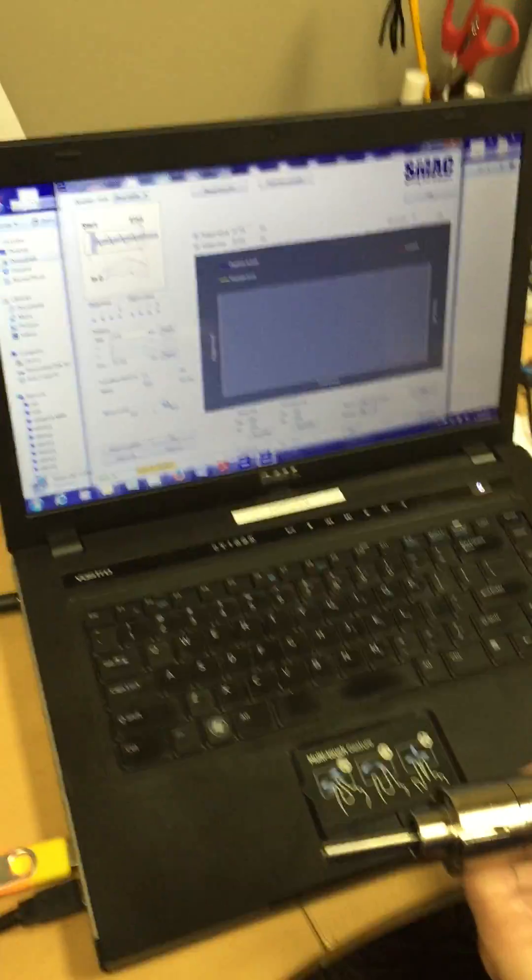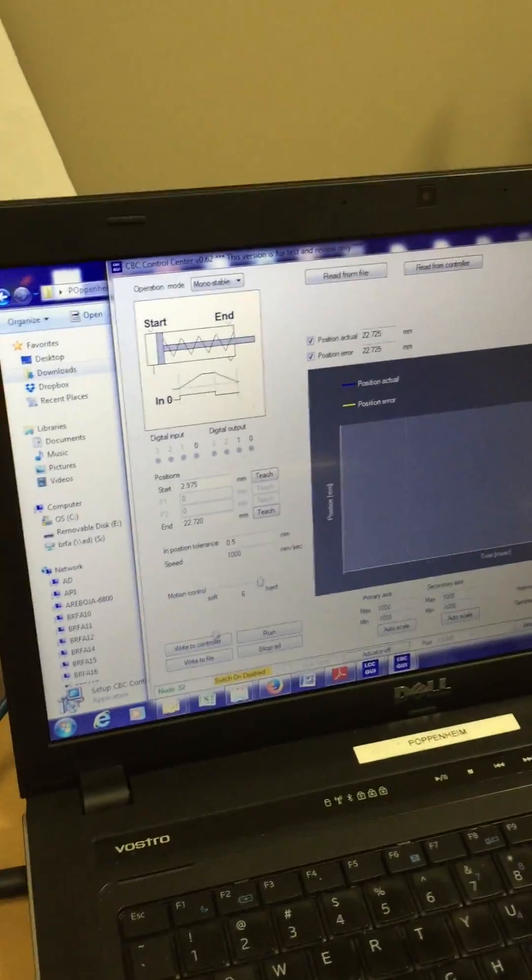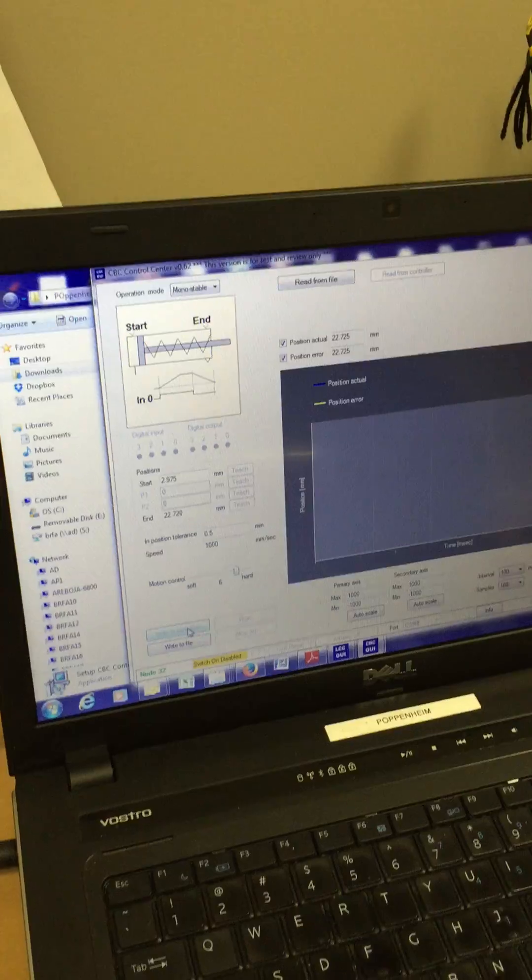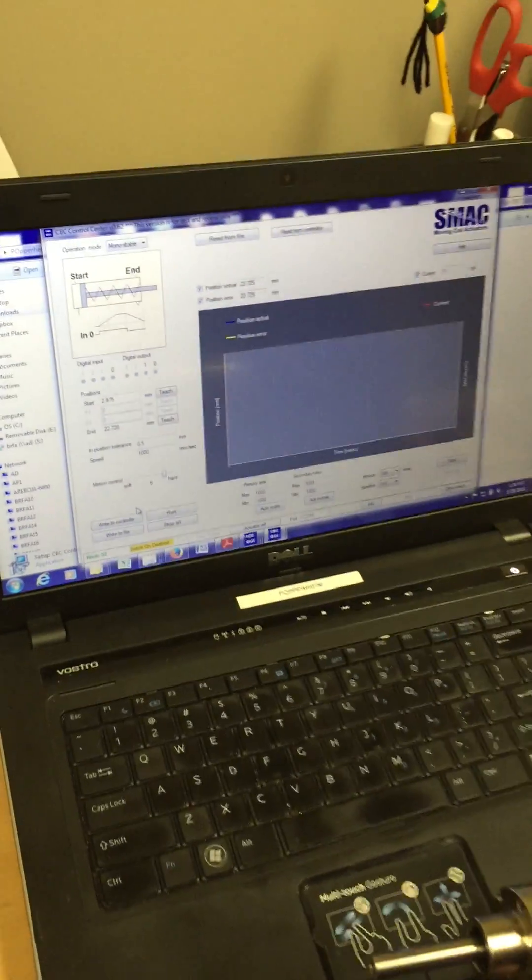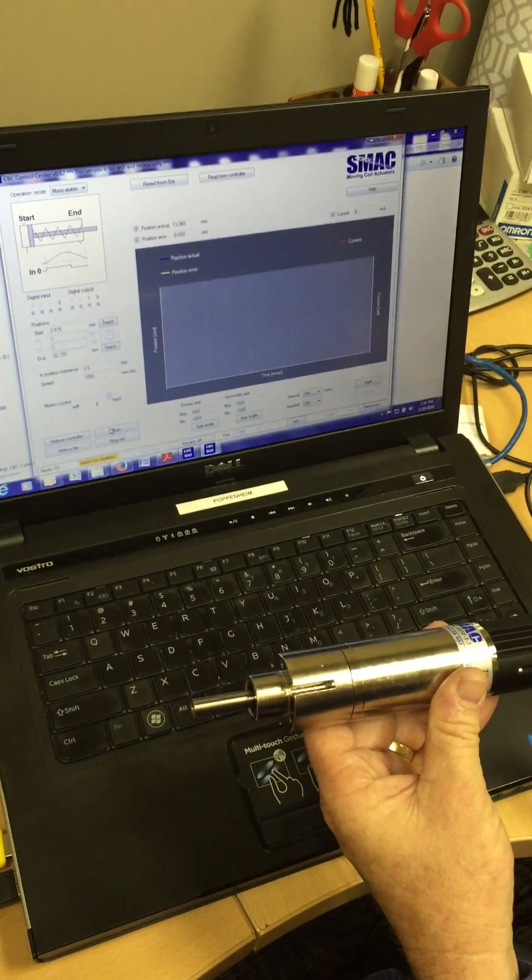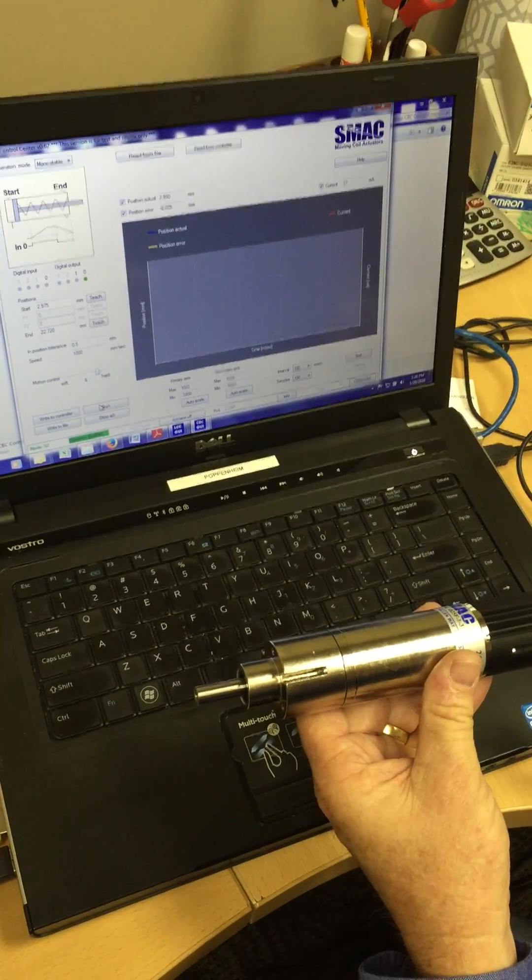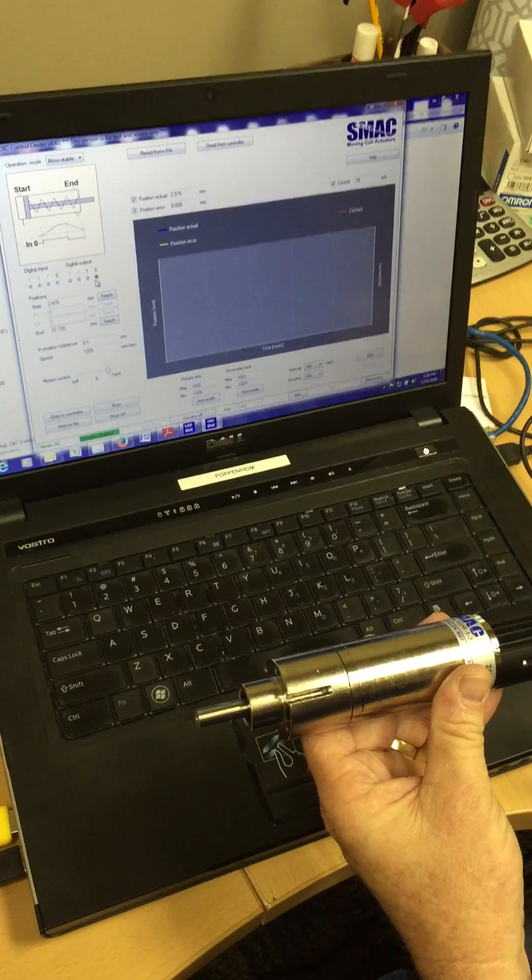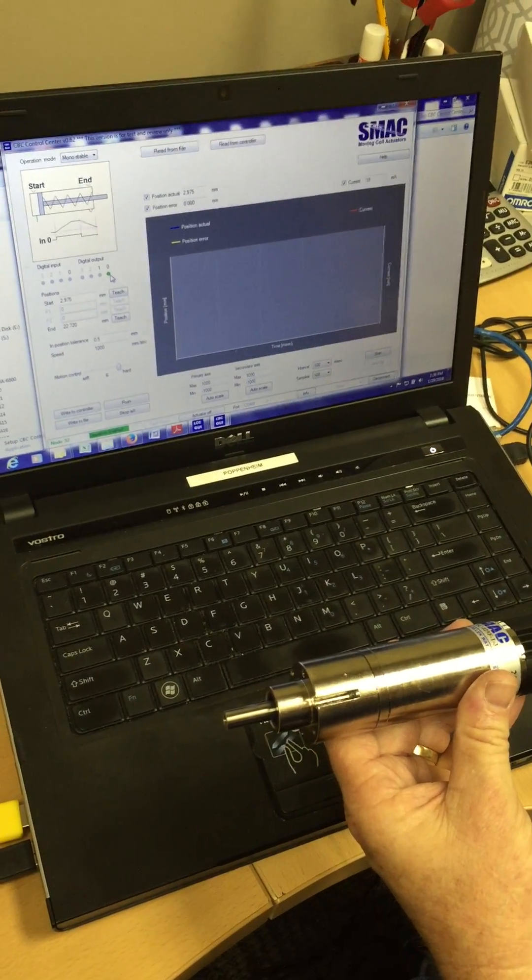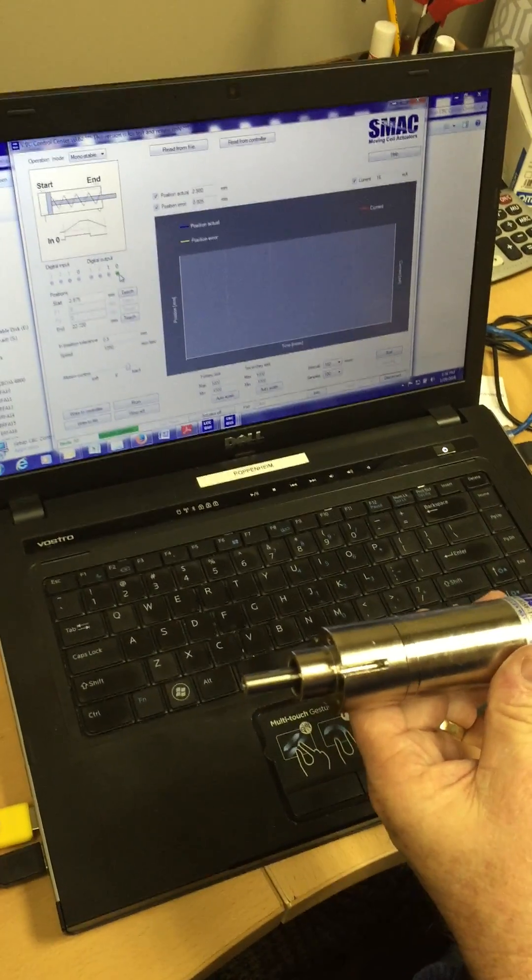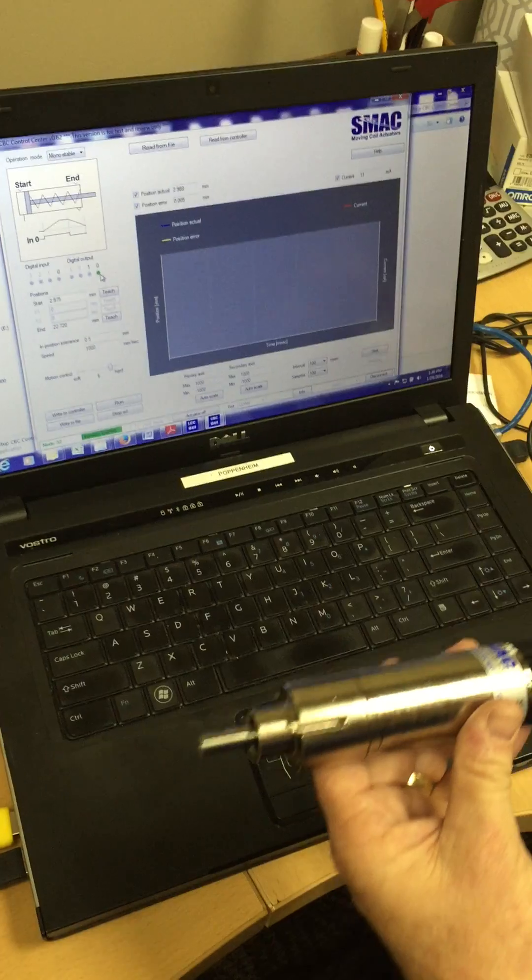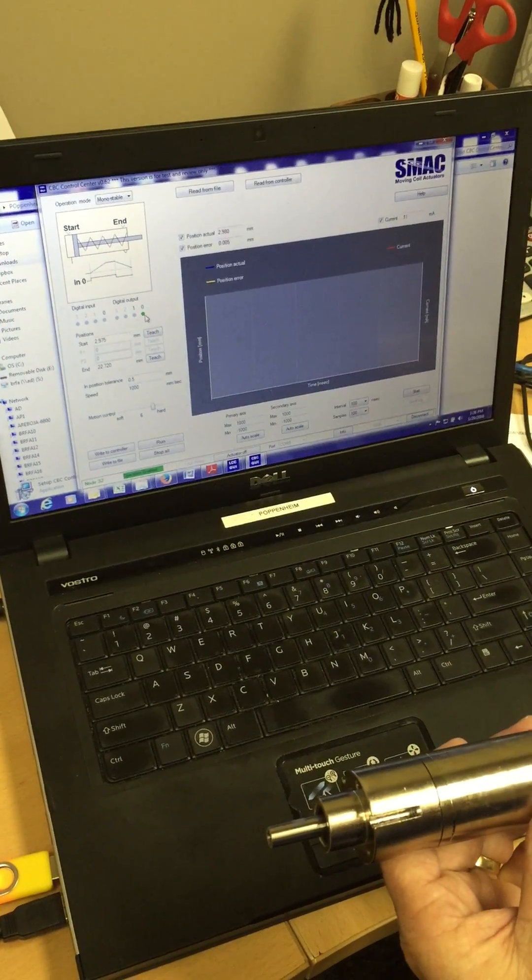So I'll bring this up a little ways. Click write to controller. It downloads it. When you click run, the shaft will come back to its number one position. At that point, you'll see that output zero is on. It's considered at its zero position or your first start position.